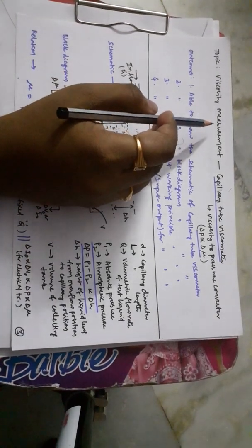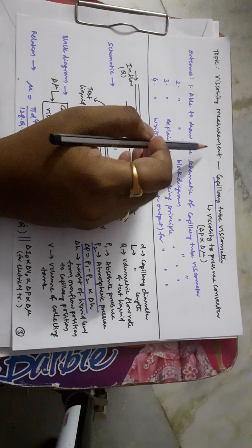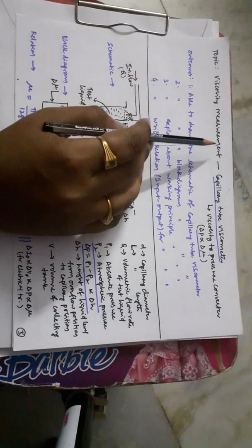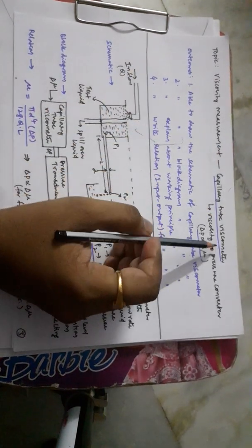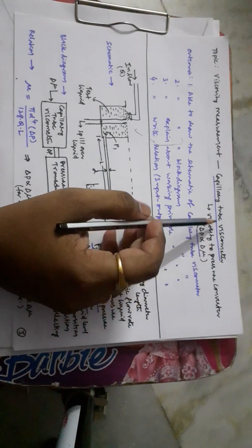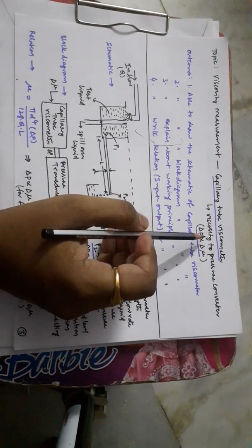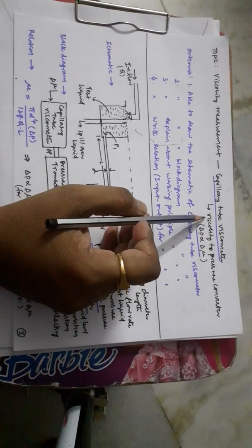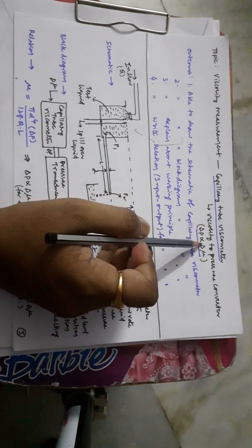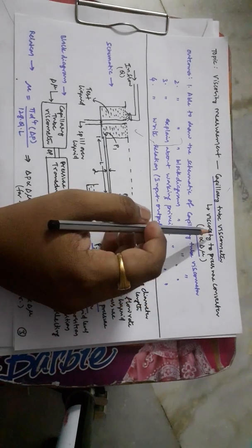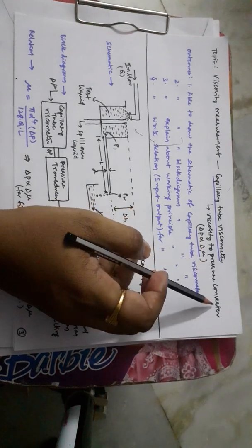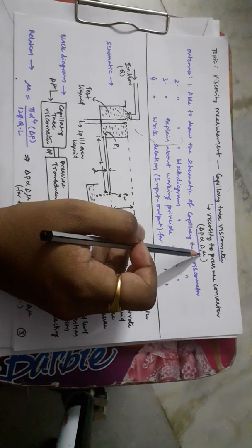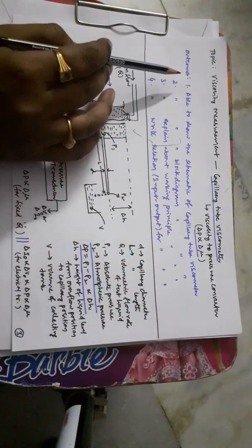In this video we will see how to measure viscosity using a capillary tube viscometer. The topic is viscosity measurement and the subtopic is capillary tube viscometer. The capillary tube viscometer is referred to as a viscosity-to-pressure converter, meaning the input measurable quantity — viscosity — is converted to pressure as part of the measurement. The output delta P is proportional to the input delta mu.